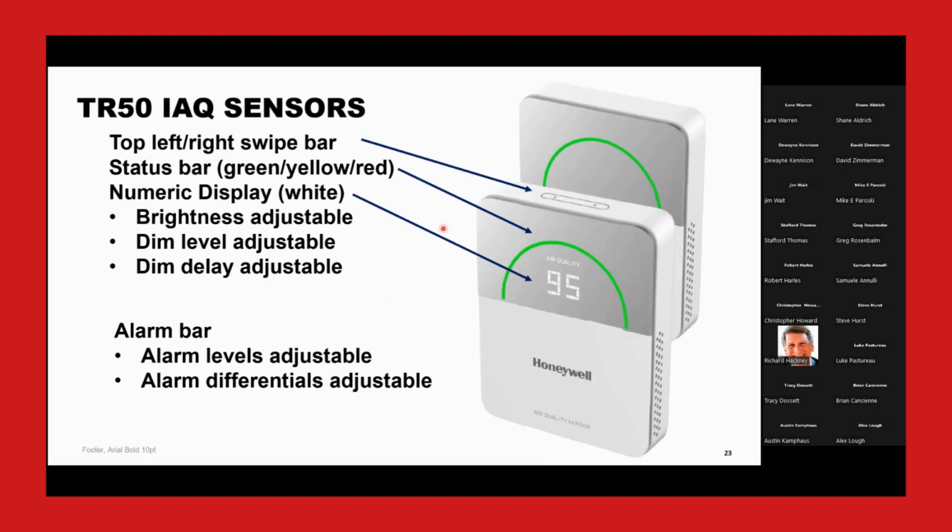All of that alarming, all of that time delay, all of that limiting has to do with the local display and has nothing to do with the Sylk, BACnet, or Modbus data coming out of it. So if it's showing a local alarm here, it doesn't mean that the BACnet point is an alarm. You can use Niagara to put your own alarm extensions on there.